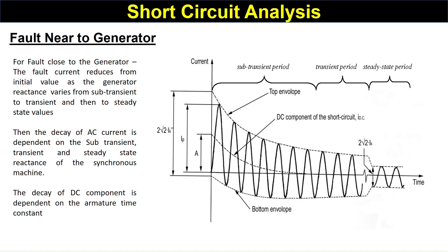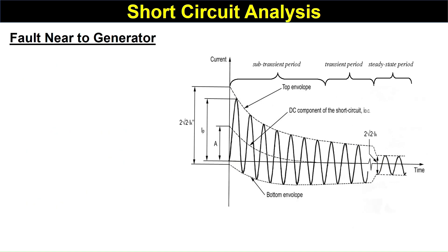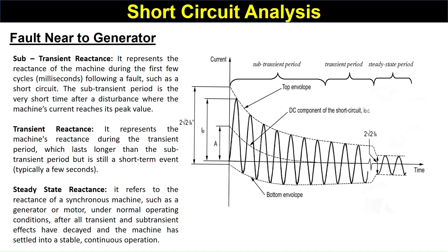The decay of the AC current depends on the sub-transient, transient, and steady-state reactances of the synchronous machine. The decay of the DC component is dependent on the armature time constant. Sub-transient reactance represents the reactance of the machine during the first few cycles in milliseconds following a fault such as a short circuit.